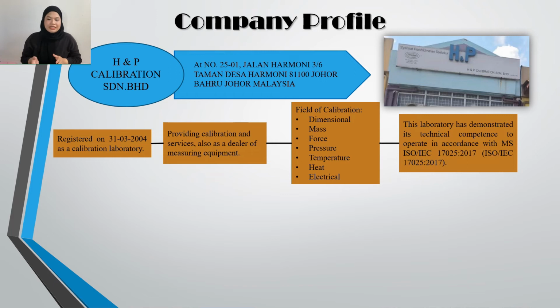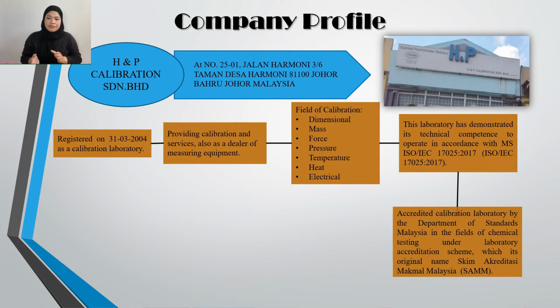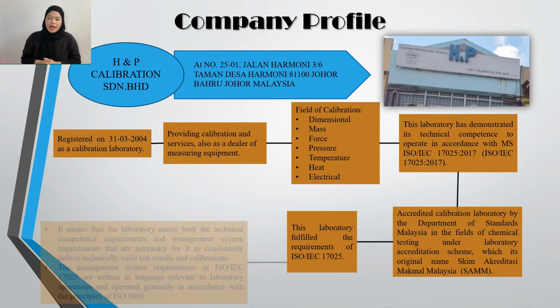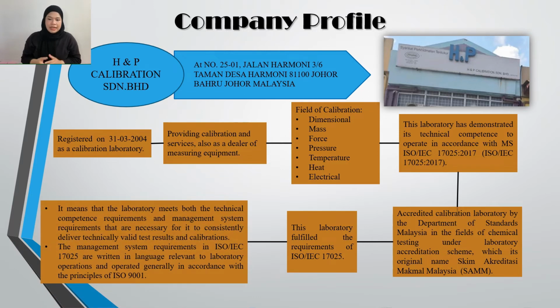This laboratory has demonstrated its technical competence in operating in accordance with MS ISO/IEC 17025:2017. Then, it is also known as a Certified Accredited Calibration Laboratory by the Department of Standards Malaysia in the field of chemical testing under the Laboratory Accreditation Scheme, SAMM. It fulfills the laboratory requirements of ISO/IEC 17025. That means the laboratory meets both the technical competence requirements and management system requirements that are necessary for it to consistently deliver technically valid test results and calibration.